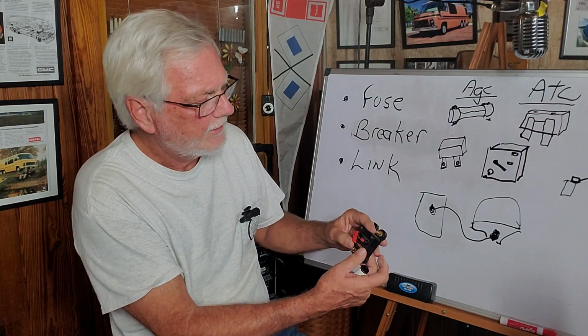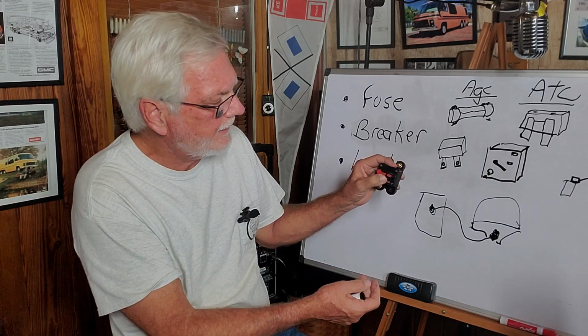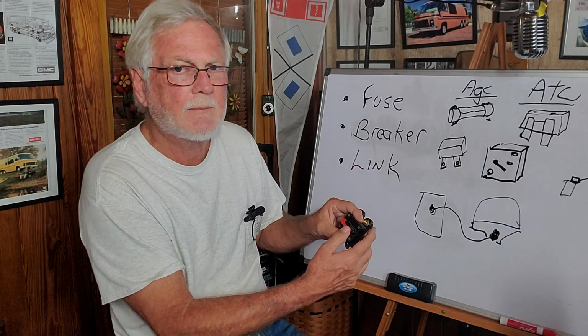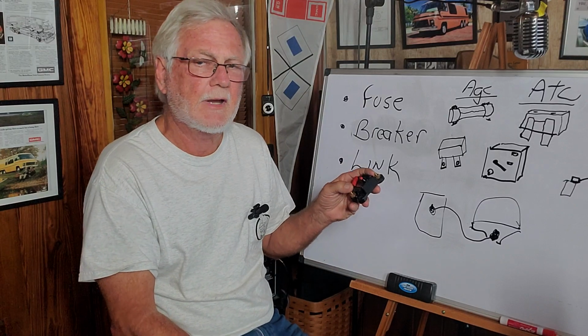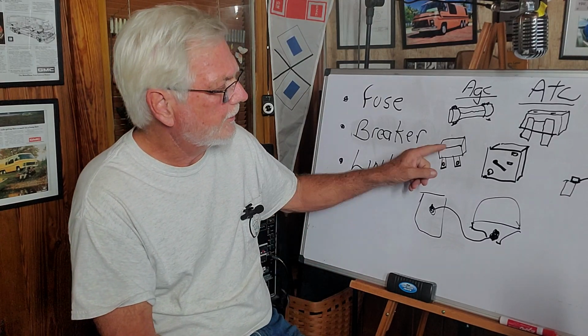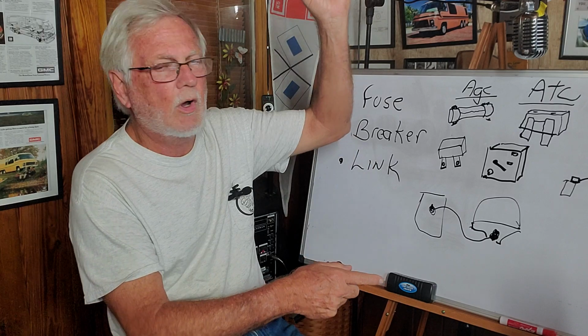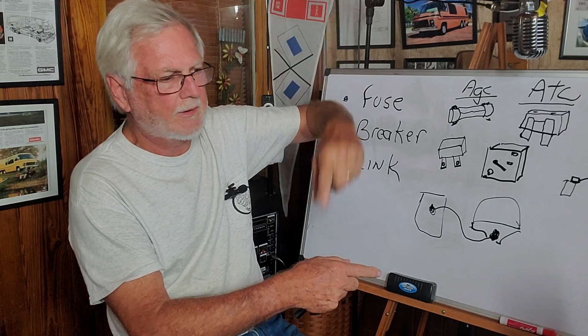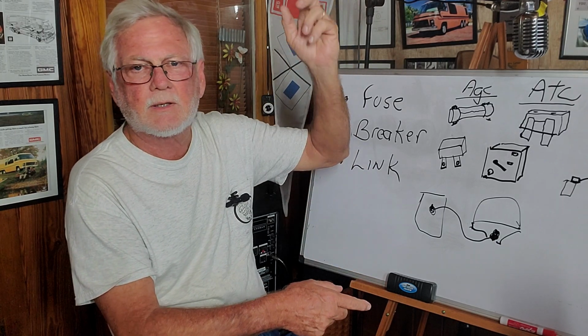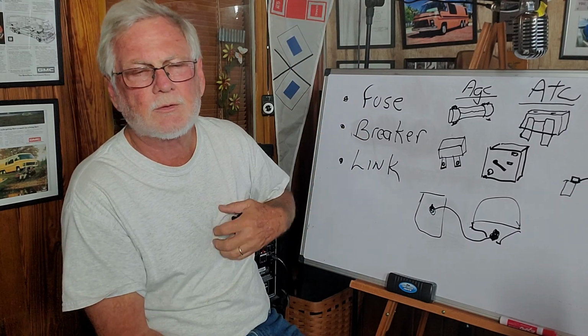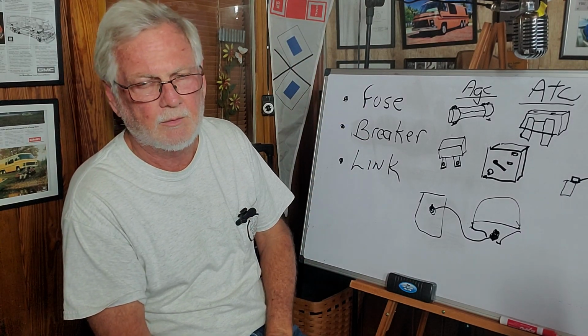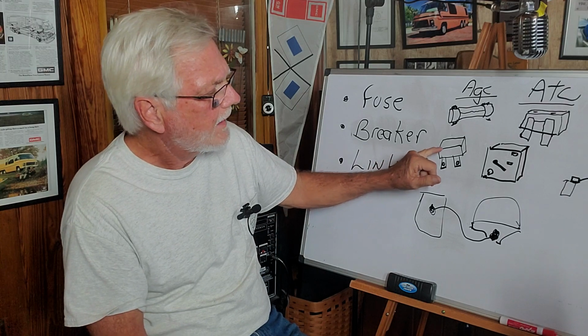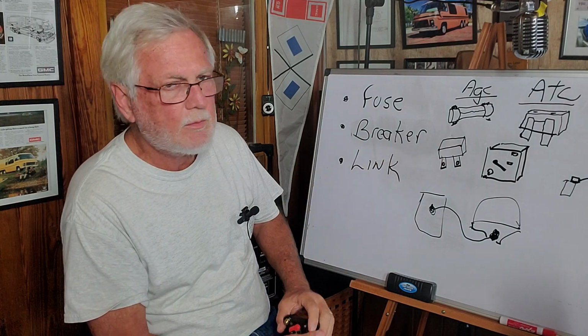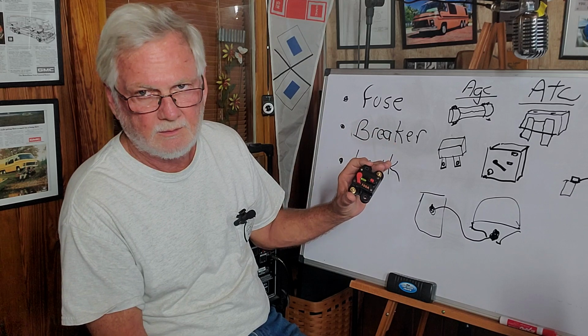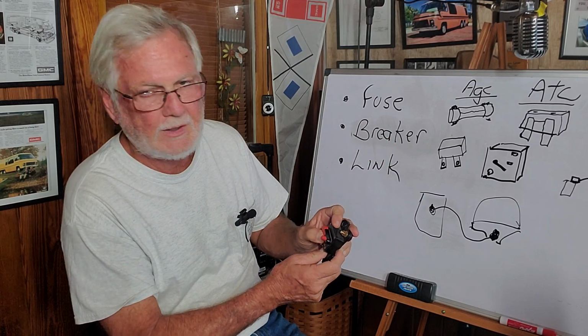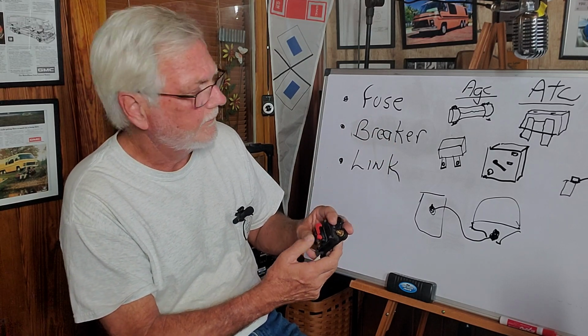Now this is not an auto reset, this is a manual reset. I kind of like manual resets, because if you have a smoke test and you have a problem and you put an auto reset in there, it opens, your problem's still there, it opens again, it goes click click click. It really could cause a problem because you've got a lot of current blowing through there. So I'm not really excited about the auto ones - I'd rather see a circuit open and then reset it myself.